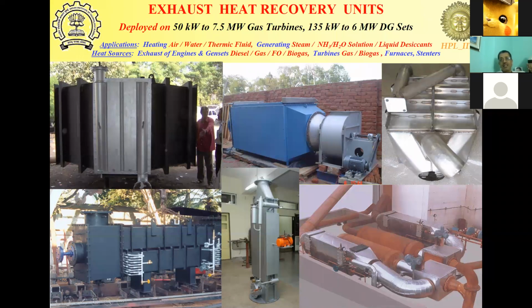Stentors are cloth processing equipment, where before the cloth is rolled out of the mills for sale, it goes through a process for heat treatment and humidity treatment, so that it doesn't shrink later on when we make and stitch our clothes. So they're pre-washed with this. And the Stenter exhaust might have water vapor, and depending upon the cloth that is used, chemical vapors will be coming out with it, which could be sticky and could deposit and condense when we try to recover heat. So these are washable heat exchangers in that case. Okay. So these are the heat recovery types.